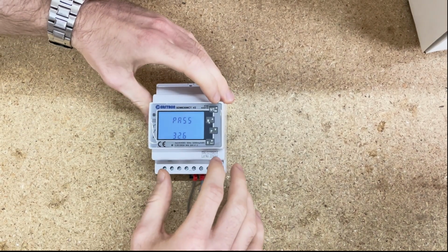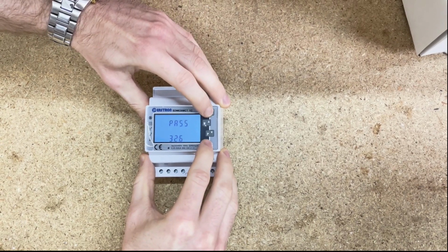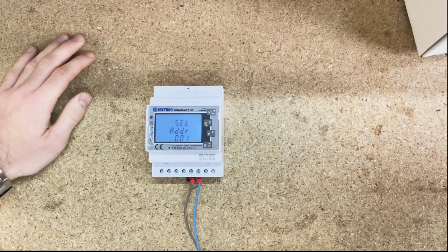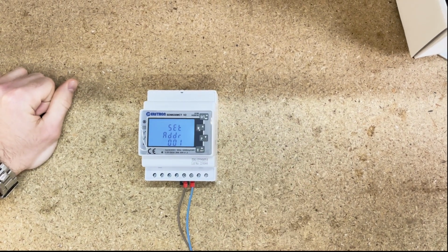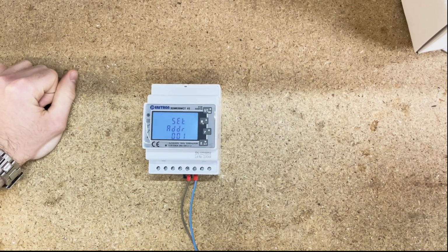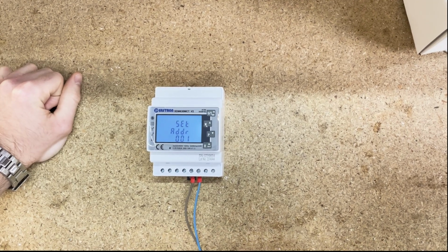What we'll do is we'll press and hold both the UI and the E button at the same time for 3 seconds. And then you can now see we're back into the settings menu using that reset code. So this is if you've already set your CT ratio and you want to reset it, or if you're getting that error code, then you'll want to try putting this in to see if that helps you.